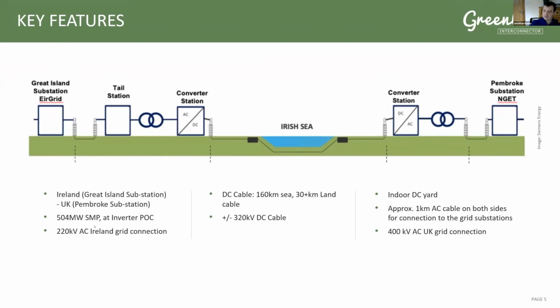It's a 220 kV AC connection on the Irish side. Then we've got the DC cable, as I mentioned, 160 kilometer DC cable, 320 kV DC. Both sides, the converter stations are identical. It'd be an indoor DC yard. On the Welsh side, then, we're coming straight into the Pembroke substation from the converter station, and that's a 400 kV AC grid connection there.